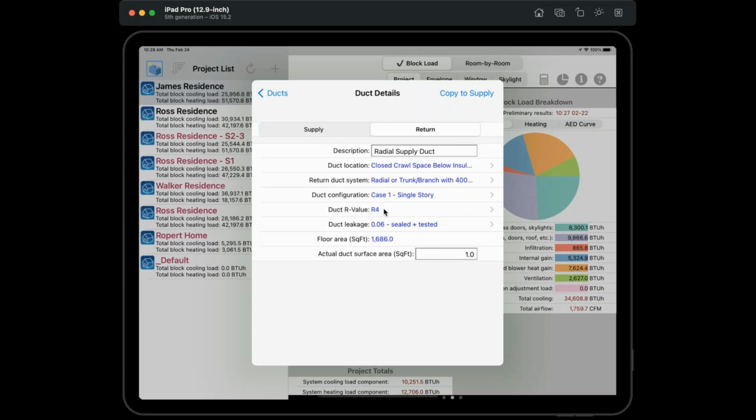That's what I was thinking of doing, because all the walls are insulated. The crawl space is sealed. It's about 3 feet tall. We got 2 4x10 registers down there. So I was thinking about forgetting about that duct, not even calling it anything. Yeah, I would say you could just ignore it. Okay. All right. Yeah, because I think that'd be the best thing.